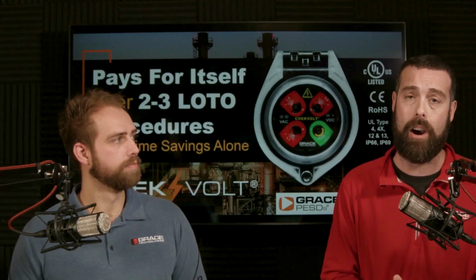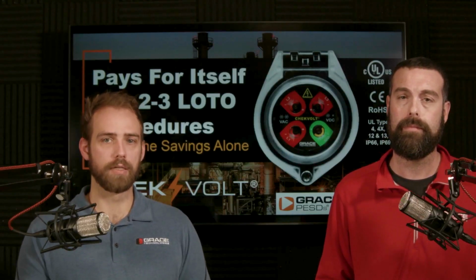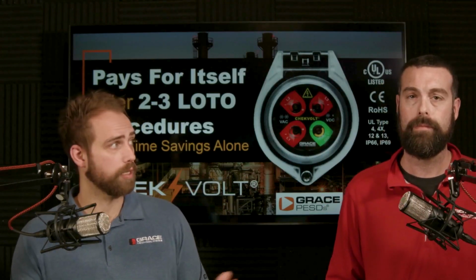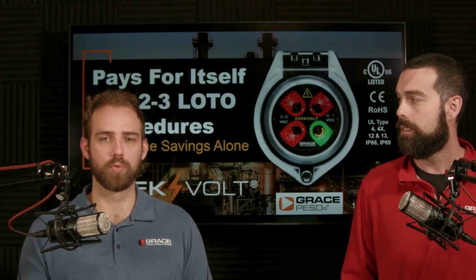But the idea here is that our product is UL listed, meeting the UL 61010 standard, and it complies with the rule within Article 120.6, the process for establishing an electrically safe working condition. Yep. So originally, when permanent electrical safety devices and devices like the AVT came out, they created an exception for those AVT type devices, I believe in 2018. Yeah. So you have 120.6 in NFPA 70E, where there's an exception essentially that includes the AVT type device. Whereas ours, for NFPA 70E 120.6, is a UL 61010 rated device, which basically qualifies as the rule for 120.6.